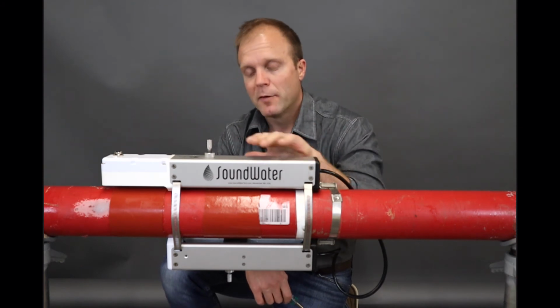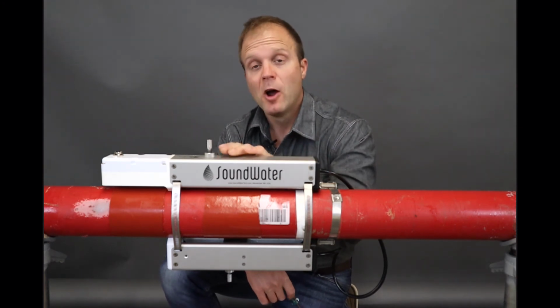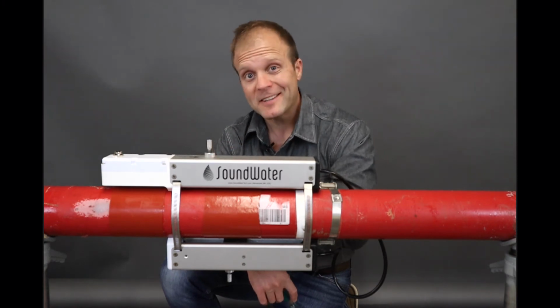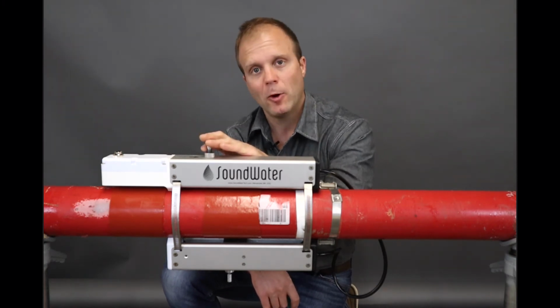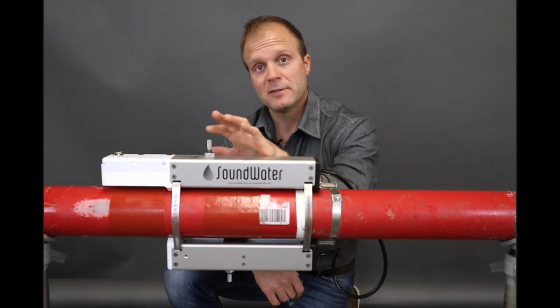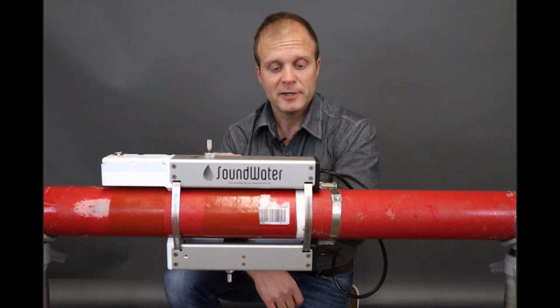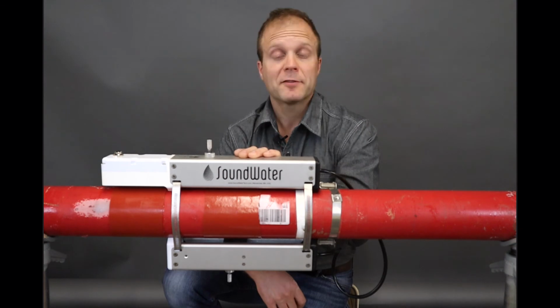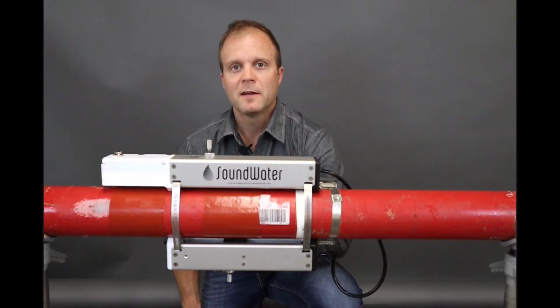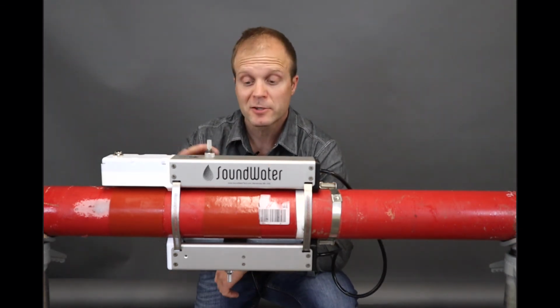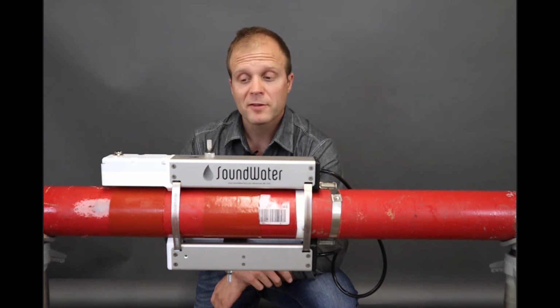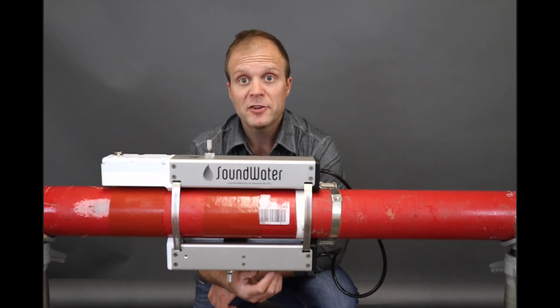Okay, for the ultrasound, as far as that's concerned, all that it needs to do is actually contact the pipe. Adding more pressure does not help at all. And at this point, actually, the transducer is not contacting the pipe, and it shouldn't be. We're going to do that after we set our transducer spacing. Okay, so now the structure is mounted to the pipe. All that's left to do is set the transducer spacing.